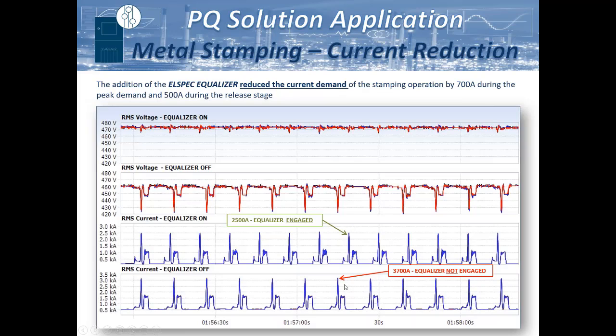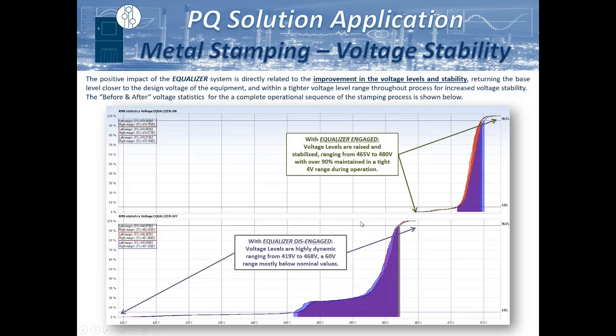You can see here a very good example of the impact on peak currents. Prior to the system being engaged, we're running about 3,700 amps, whereas with the system engaged, we're only running about 2,500 amps. This has a very large impact on equipment longevity because we're reducing the amount of heat that's produced and transmitted to all the components, and heat leads to wear, obviously.